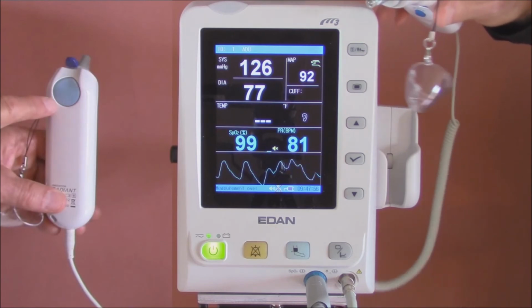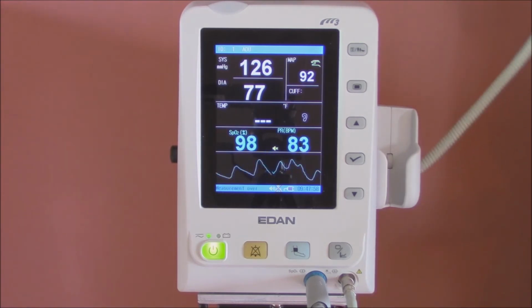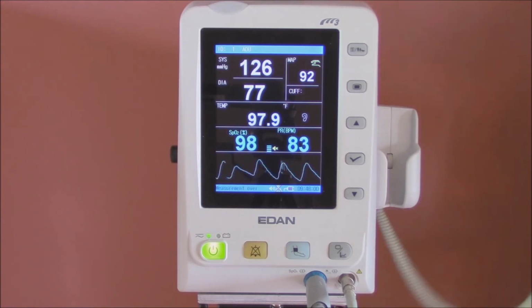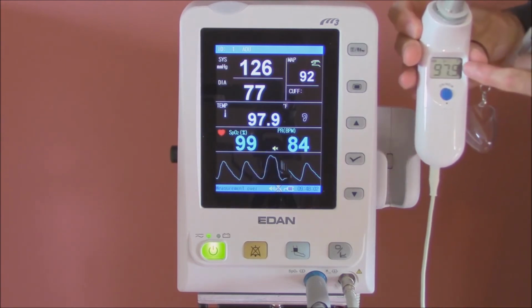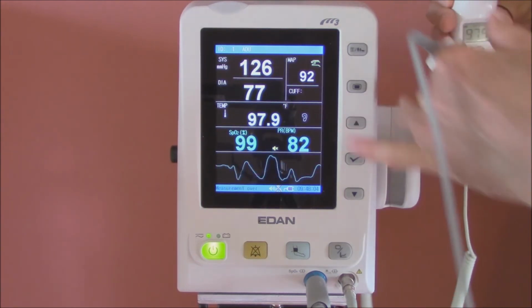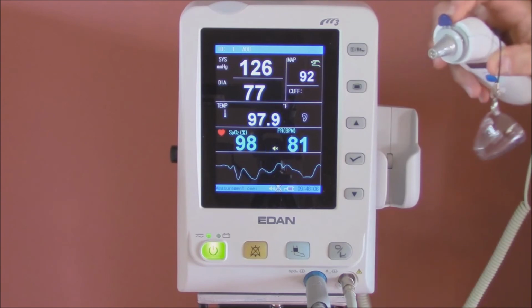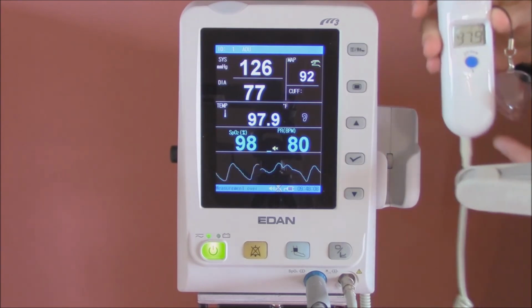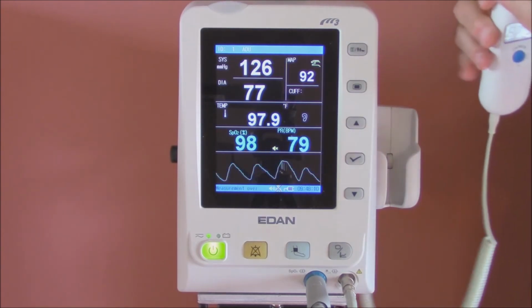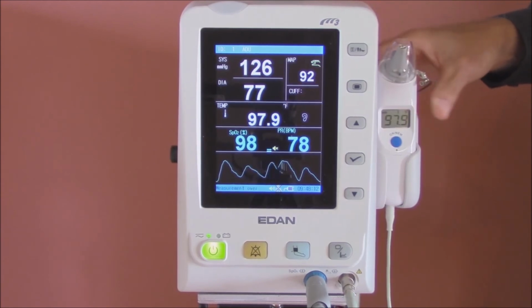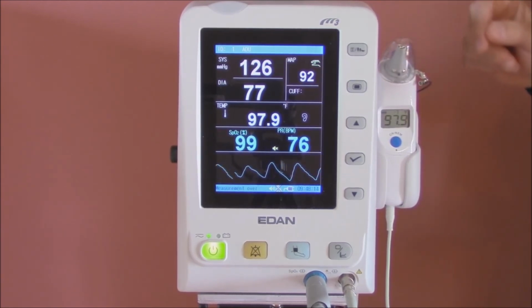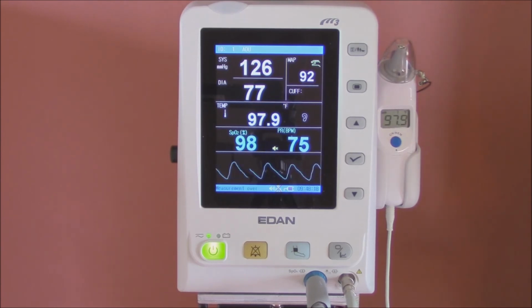Press the blue button on top of the tympanic thermometer until the thermometer beeps. The temperature will display on both the LED display on the thermometer and also on the vital system. Eject the probe cover by pressing forward on the blue release tab and place the cover back on the unit. Please be sure to always have the probe cover on the unit when not in use, as dust will accumulate on the optical end of the probe cover and cause the thermometer to read low.